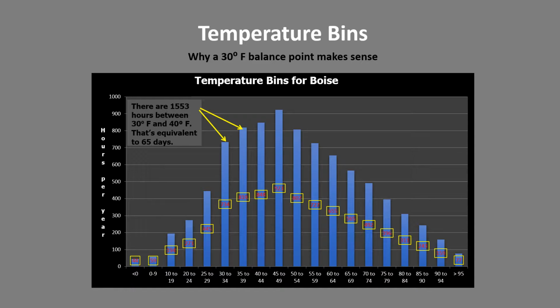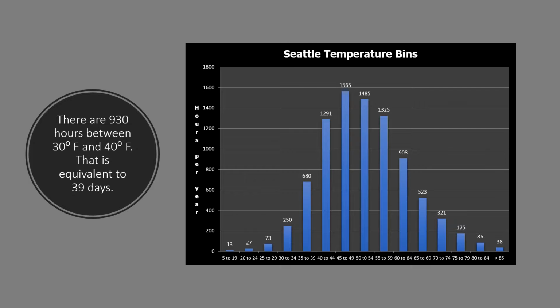So if you drop the balance point from 40 all the way down to 30, that's 1,553 hours, or the equivalent of 65 days that strip heat would have to come on to help heat the house. And boy, that's a lot of electricity. Let's take a look at Seattle. It's obviously more mild, but even in the mild Seattle, there's 930 hours between 30 and 40 degrees F. That's equivalent to 39 days. So even in mild climates, getting a balance point of 30 is critical to energy savings and client satisfaction.